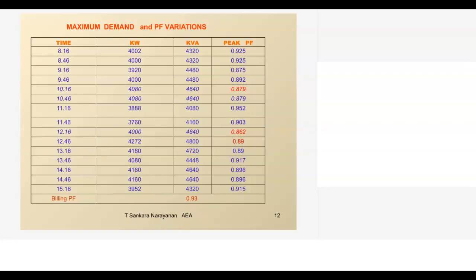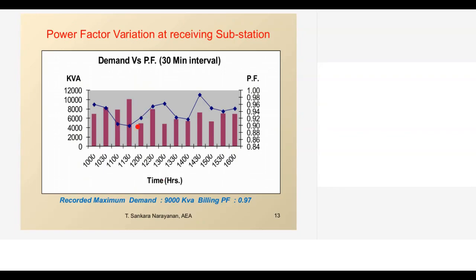So again, the industry started, we will go for an APFC panel. See, this is a case of an APFC panel. This is again a 9 MVA load. Billing power factor for this plant is 0.97. So when the audit was started, they told us everywhere they have APFC. They have more than 12 or 13 substations, and in all the substations APFC was there. Still, when we put the power analyzer and started monitoring on an hourly or half hour basis, the power factors were going down to 0.88 or 0.9. That means, though APFC is there, APFC is not ensuring that my peak demand or peak power factor is maintained. It is overall taking care of the set point and providing the billing power factor.